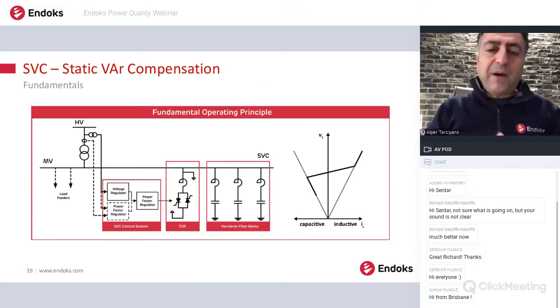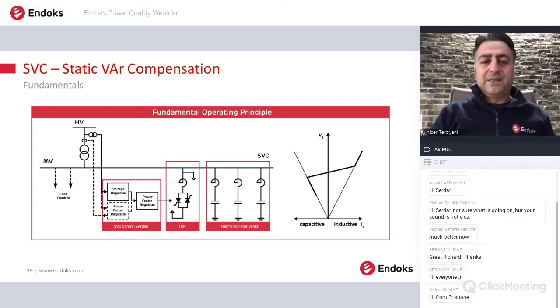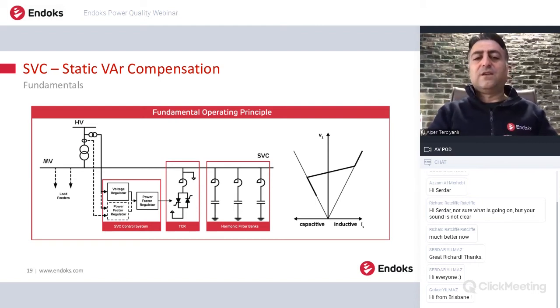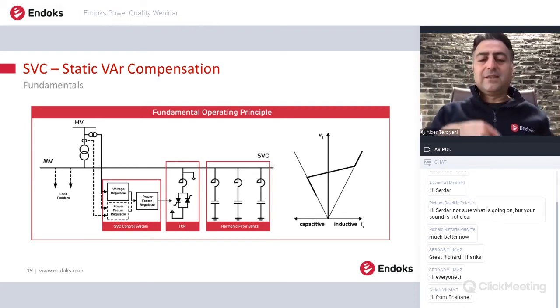And another reactive power compensation system is the SVCs, static var compensators. The word static comes from the semiconductor itself. I mean, actually, it's a dynamic solution. It is varying very fast. It acts very fast. But since we are using semiconductors, we call this solution static power compensation. So static denotes the semiconductor device, not the operation behavior of the system actually.